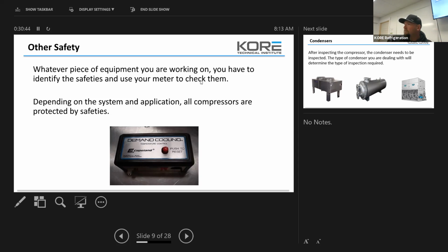Most of the time it's 35 for what we deal with on the rack, the discs and stuff, the inlines. So as long as we're sitting around 35 net oil pressure. That's the oil pressure minus the suction pressure. Your suction pressure is going to be lower, and your oil pressure is going to be higher. So if you had a 75-pound oil pump pressure, I would want to see 45-pound suction pressure or lower. That gives me that 35, or I'm sorry, 70. If I had a 75, I would want a 40 or lower. So I'd get that 35 net.